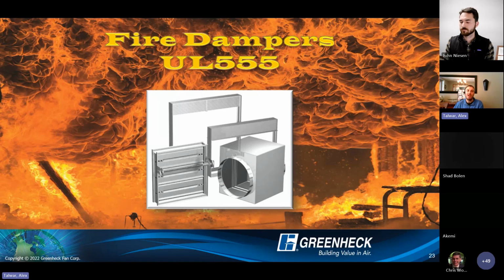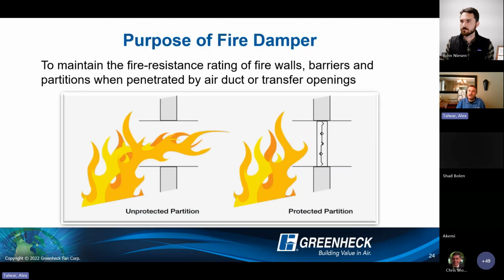So I'm not going to go too much deeper than that into smoke control systems. I'm really going to stick to the main requirements and things to be aware of in terms of the products themselves. So for fire dampers, we will start with UL 555 fire damper certification. This one's the good pictorial, the fire dampers for dummies slide, right? If you don't have a damper, then the flame could get through the ducts. So we put a damper in the duct to prevent the spread of the flame. But it is a good side-by-side pictorial to give you an idea. And again, to re-illustrate the point that these products are preventing the spread of flame from one area to the other and maintaining the fire resistance rating of the construction that it is installed into.